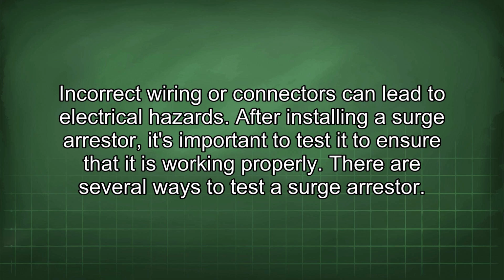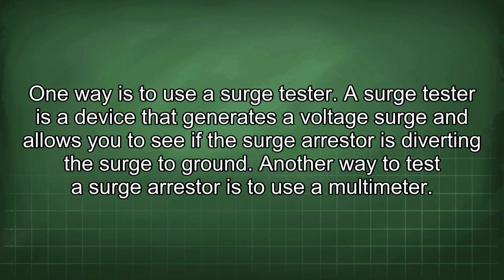After installing a surge arrestor, it's important to test it to ensure that it is working properly. There are several ways to test a surge arrestor. One way is to use a surge tester. A surge tester is a device that generates a voltage surge and allows you to see if the surge arrestor is diverting the surge to ground.